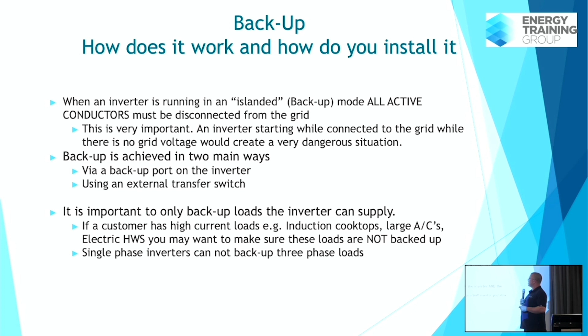You also need to make sure that your backup loads, whatever it is that you're backing up, your inverter is capable of backing up. If a customer has a 30 kilowatt split system and you're installing a 5 kilowatt battery inverter, you can't back up their split system. It's not going to work. If they've got an enormous pool pump, you can't back up their pool pump, right?